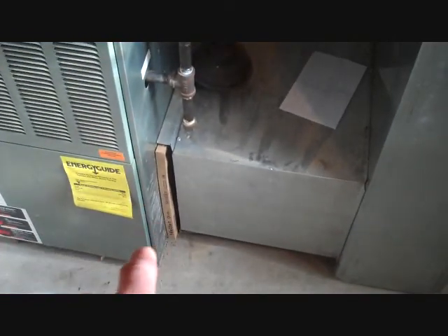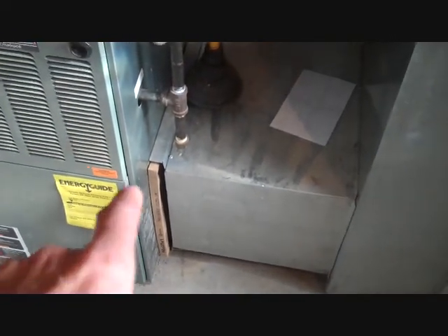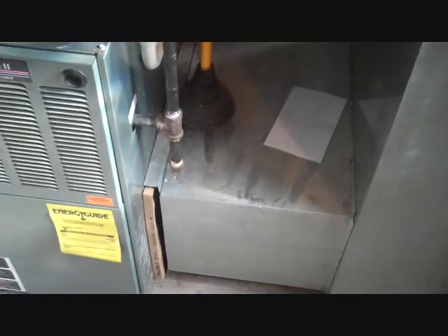Also, when I was measuring, I noticed that the filter box going across is undersized, and they didn't cut the hole large enough in the furnace return, which is choking the furnace return air. And also they came in with a properly sized duct riser, and up here choked it down to a smaller size.